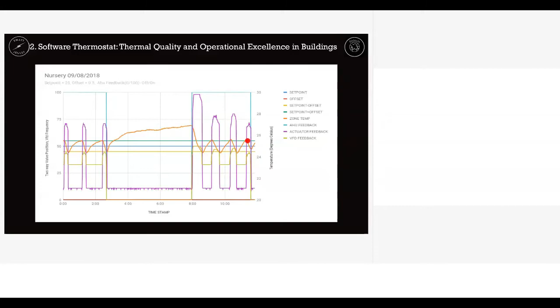So this orange line is playing with the comfort. When the orange line is here, the two controllables, the fan speed and the amount of cold water, are increasing. Again, when the orange line comes here, the area is overcooled or at the lower limit, so the fan speed goes to minimum and the valve also shuts down. This toggling of the controllables is fetching a considerable amount of energy savings, and that is another way to save energy from the building.